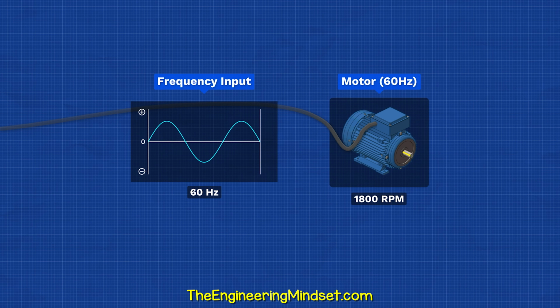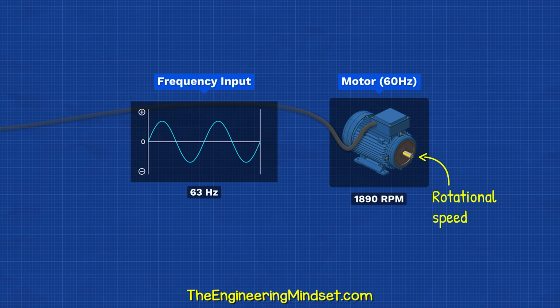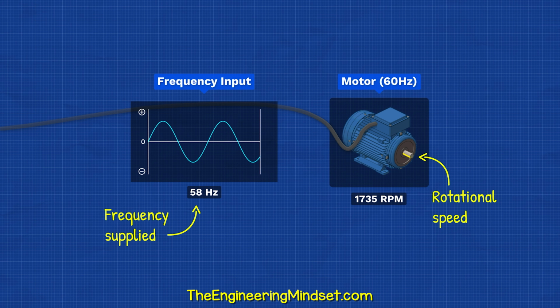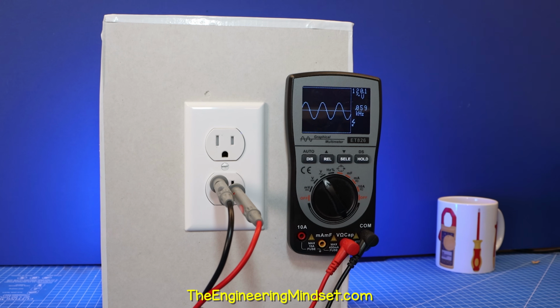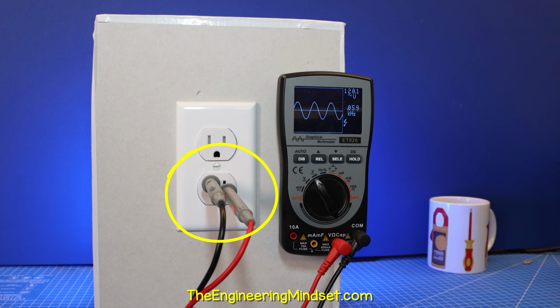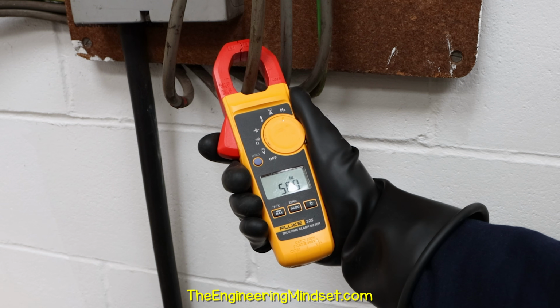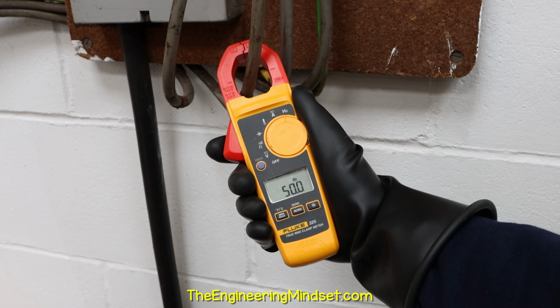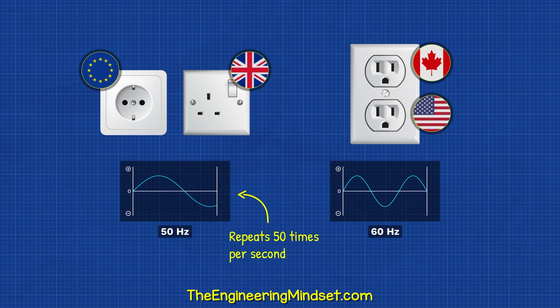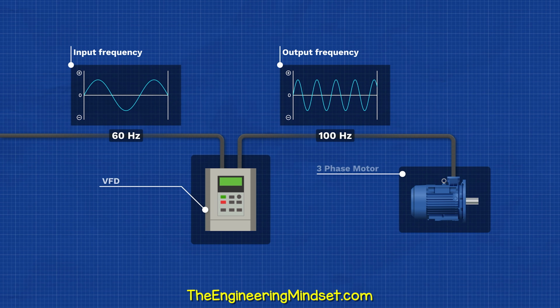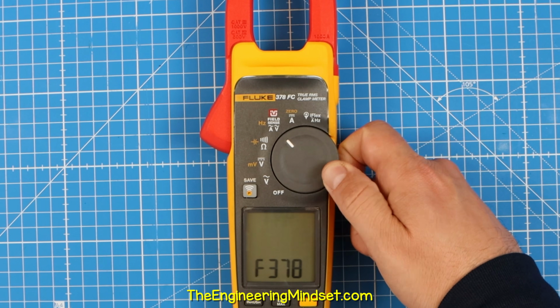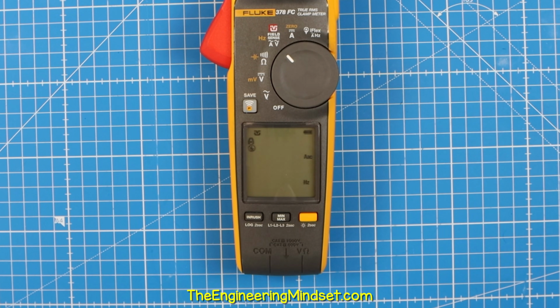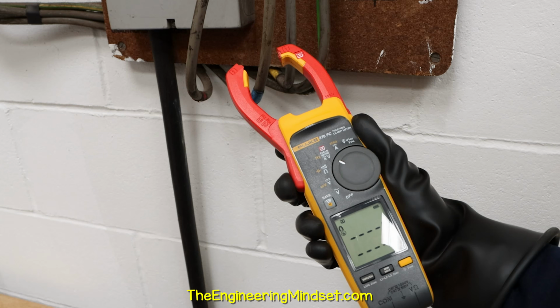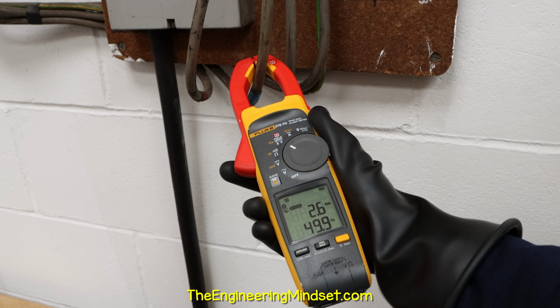This AC motor is rated for 60 Hz. Its rotational speed depends on the electrical frequency which it is supplied with. With a multimeter, we need to connect into the circuit, but with a clamp meter, we just select the frequency function, then clamp around the wire, and it will display the value. It's typically 50 Hz in Europe and 60 Hz in North America, but some devices can vary their output frequency. With this meter, we just select the field sense function, then press the yellow button to switch to frequency. We then clamp around the wire and it displays the value.